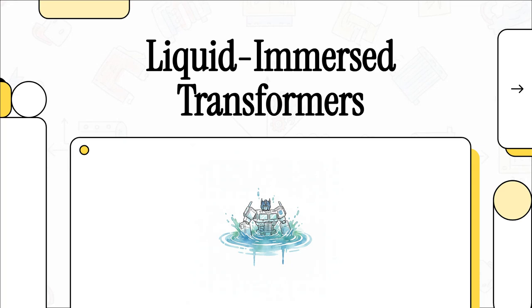So, if you remember our earlier chats, dry-type transformers, like the Resibloc, rely on a solid resin cast coil just sitting in open air. Great for simplicity, right? But they definitely have their limits. Today, we're flipping the script and looking at the alternative, liquid immersed transformers. We're going to break down how they operate by mastering three very specific design axes: winding configuration, insulation fluid, and classification society approvals. Let's just dive right in.